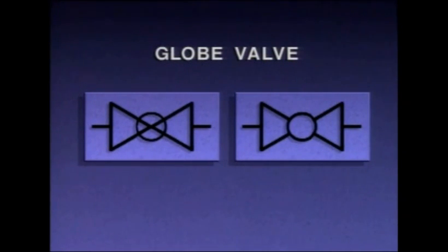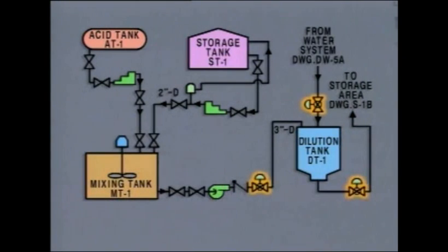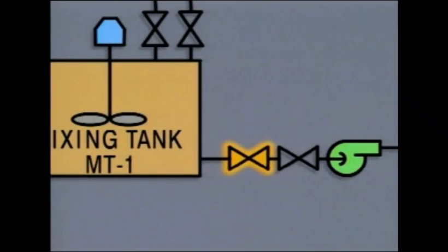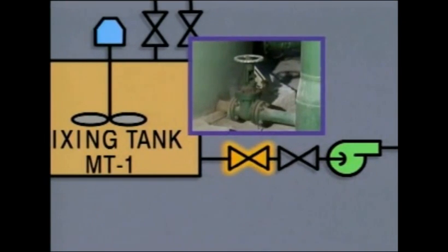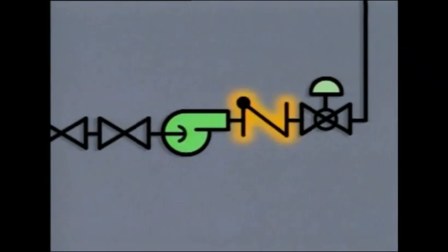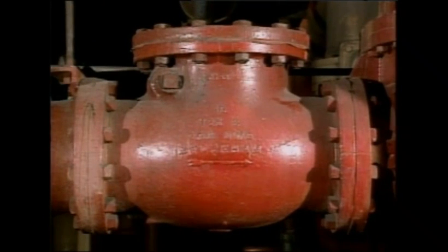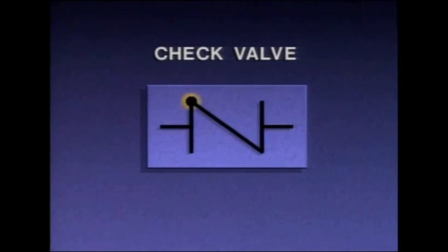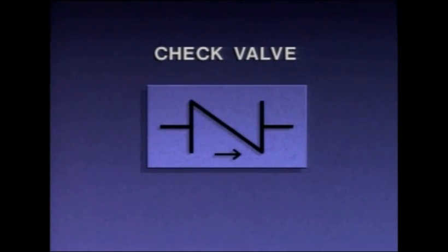Globe valves are often used to regulate fluid flow because they can be partially opened or closed to adjust flow rate. You may see globe valves represented on diagrams by either of two symbols. There are three globe valves — one in each line to the dilution tank and one in the line to the storage area. Gate valves at the bottom of a tank are normally positioned fully open to allow flow or fully closed to isolate equipment. Check valves are designed to allow fluid flow in only one direction. There's usually some notation indicating the direction of flow — for example, a dot indicates the side where fluid enters. An arrow symbol may also be used to indicate direction of flow through a check valve.